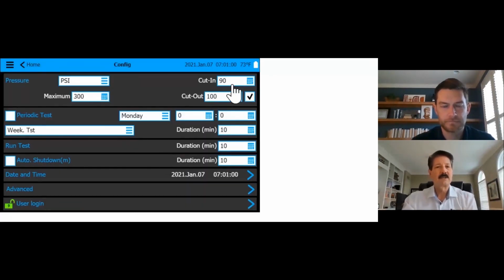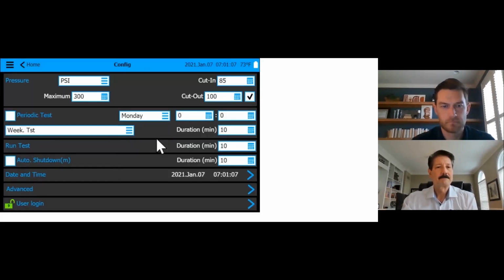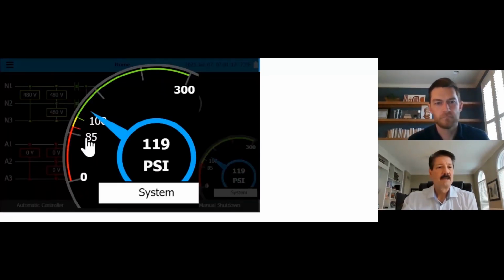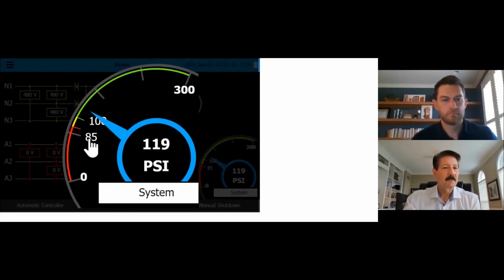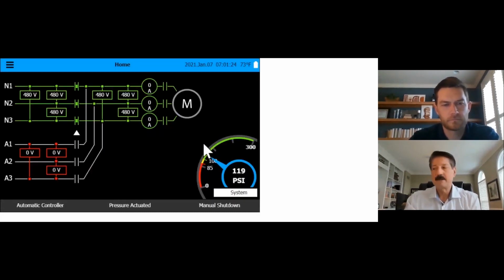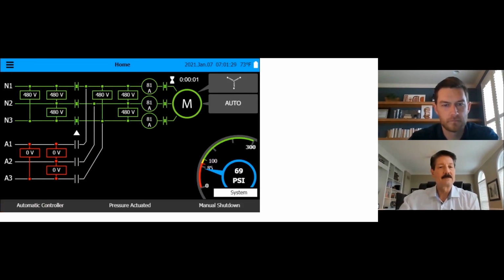All right, let's get right into it. The cut-in. I want to change the cut-in. I really want to have it set at 85. And honestly, I'll leave the cut-out at 100. So I'll go back to home. You see, just a couple of simple keystrokes. My turn-on pressure is 85 PSI. My turn-off is 100. I apply this adjustment here on my demo, and again, when pressure drops below 85, we have a pump on demand. I need to manually shut this down.